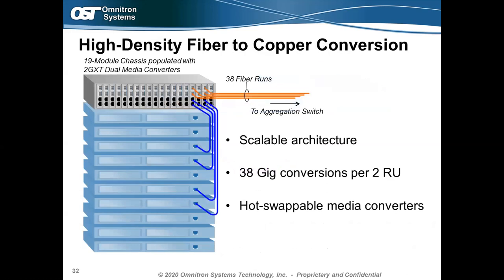Dual-channel media converters can also be used in a chassis configuration. Fully populating a 19-slot iConverter chassis with 2GXT dual-channel media converters yields up to 38 fiber-to-copper conversions in a 2U rack space. It's a scalable architecture — plug in different cards as needed, cover blank slots with panels, and all media converters are hot-swappable.